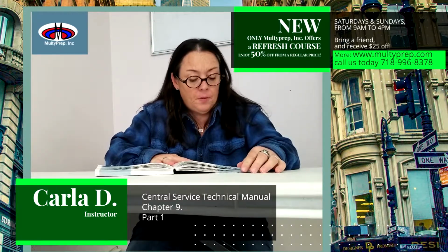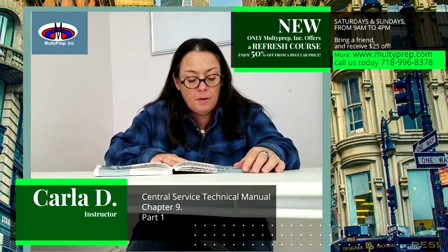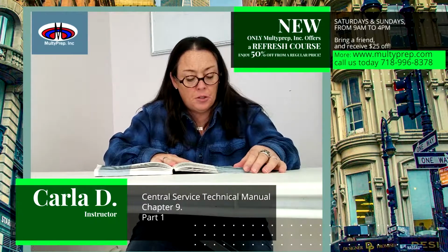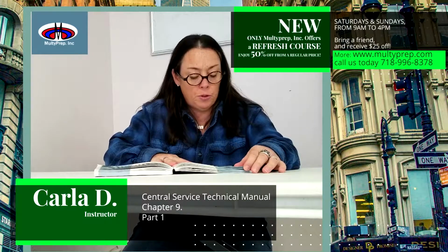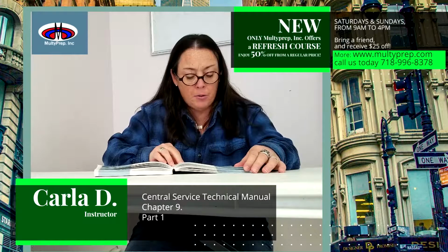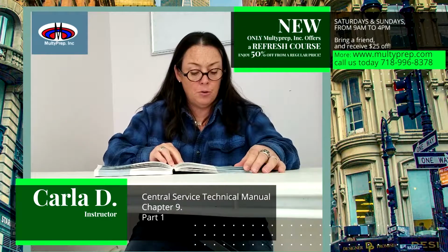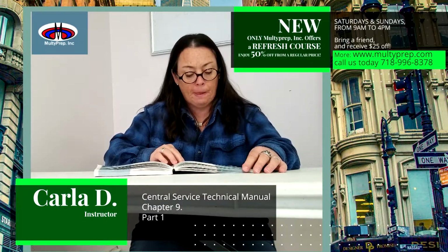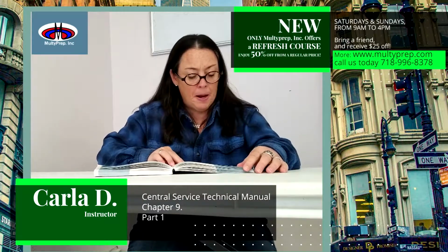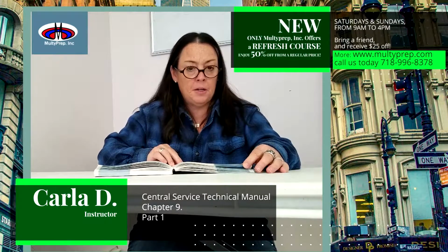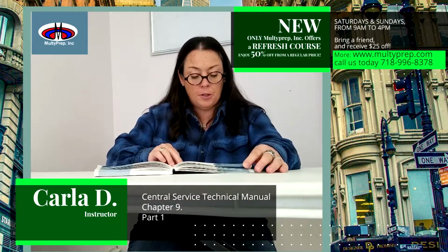Glutaraldehyde. Glutaraldehyde is a high-level disinfectant, or HLD, used for semi-critical devices such as endoscopes and ultrasonic probes. Glutaraldehyde is compatible with materials used in many modern medical devices and can be used to process medical devices containing heat-sensitive materials. It kills microorganisms by alkylation of proteins. Glutaraldehyde is usually a clear liquid that turns color when activated. See figure 9.11 for an example.